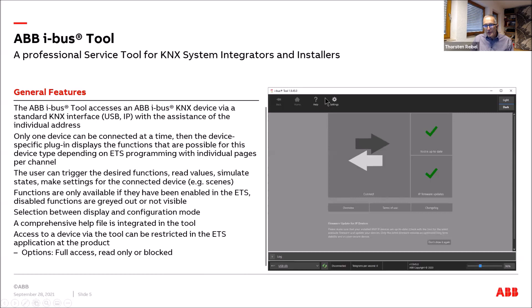A comprehensive help file is available — click on 'Help' in the toolbar and context-sensitive help appears on the right side. You can also restrict access via ETS parameters for each product: full access allows both reading and writing via the i-bus tool; read-only means you can only see states and actual values; or you can completely block access via the i-bus tool.